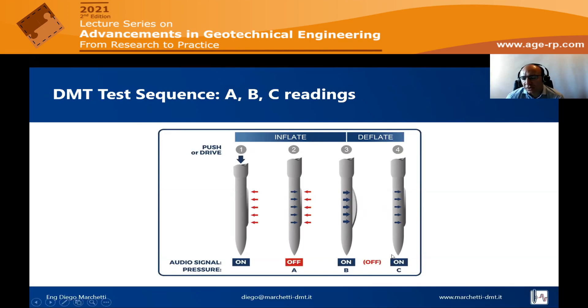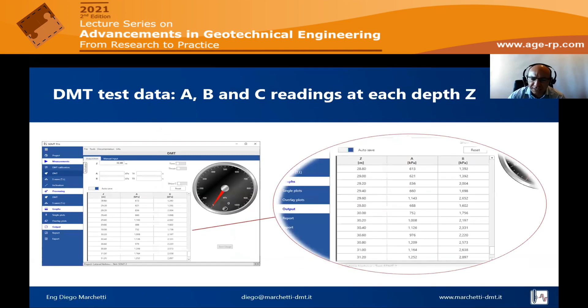The operator continues to inflate. When the membrane has expanded 1.1 millimeter in the center, the contact goes back on and the B reading is obtained. Then you deflate, and when the contact goes back on, the C reading is obtained. So basically, a DMT test consists in taking every 20 centimeters 2 pressure readings, A and B, and eventually the C reading from time to time. We will see the meaning of these readings in the next slides.